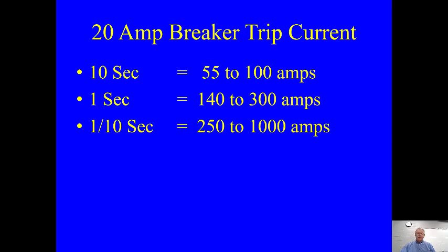Now, does that change our perspective on the hazard of resetting a breaker trip? If we have 1,000 amps going through wire that is only good for 20, and I know we're just starting class, number 12 wire is good for 20 amps according to National Electrical Code. Okay, sometimes 12 is good for a little more than that, but for your home, 12 gauge wire is good for 20 amps. So you're passing upwards of 1,000 amps through that wire. So if you trip it, reset, trip it, reset, trip it, reset, what are you doing to that wire? What are you doing to all the insulation on the wire in your home? You're heating it up and you're starting to damage it.